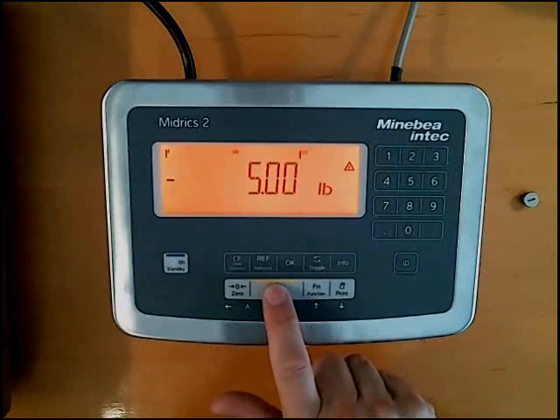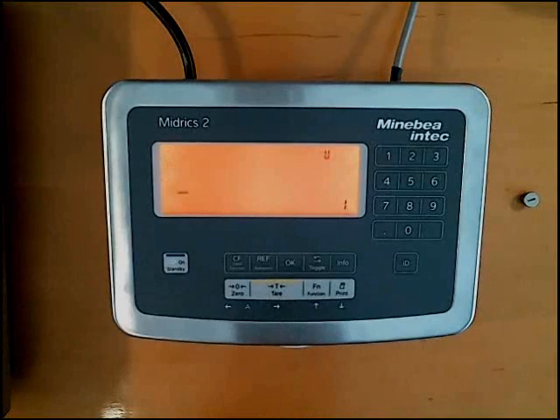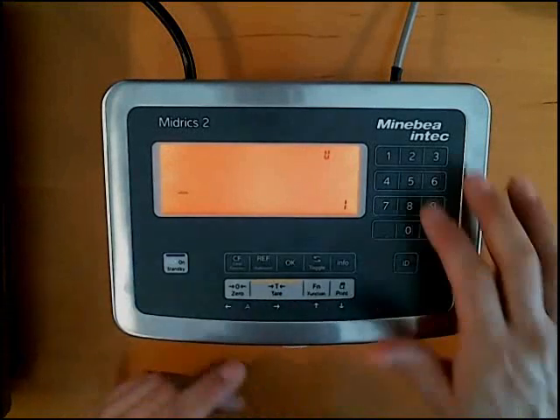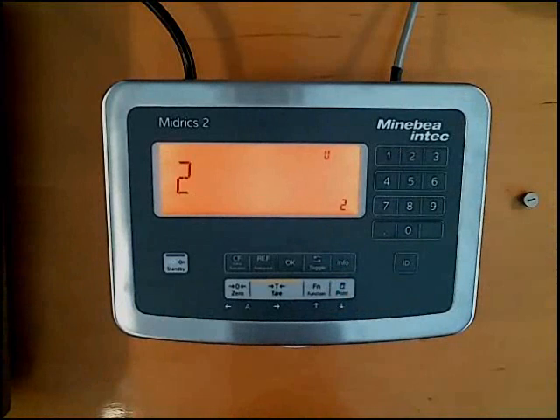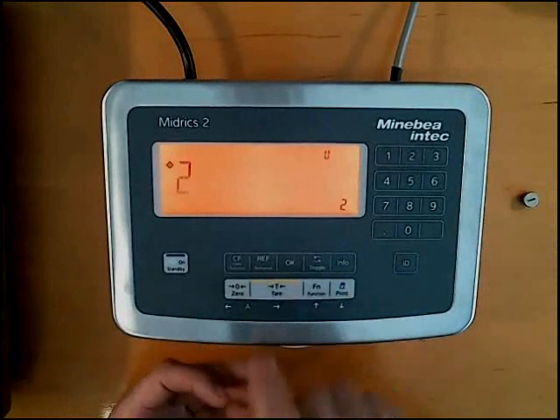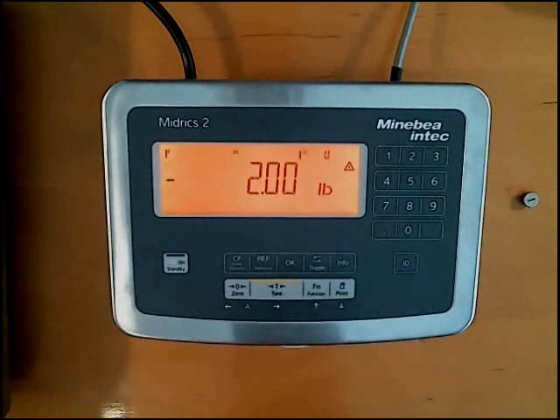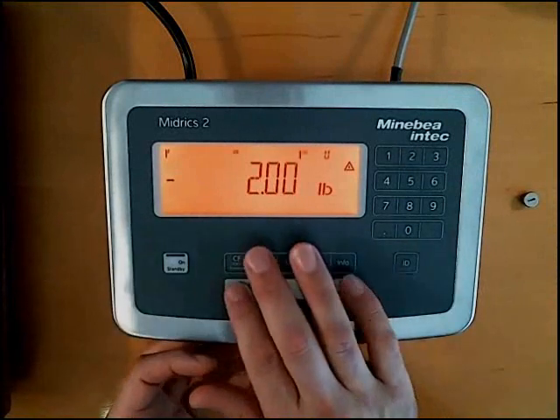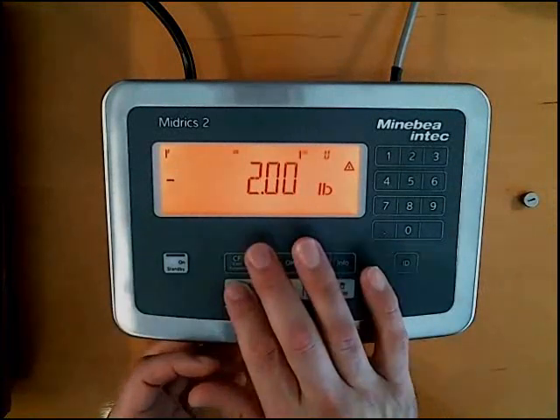All you have to do is press and release the tare key. You'll see a blank screen with the flashing cursor. Type in the calibration weight that you'd like to use, for example 2, and press tare again, and you'll see that it's showing -2. Okay. Well, I'm going to use 5, so I'm just going to show you that again real quick so you can see how that works.